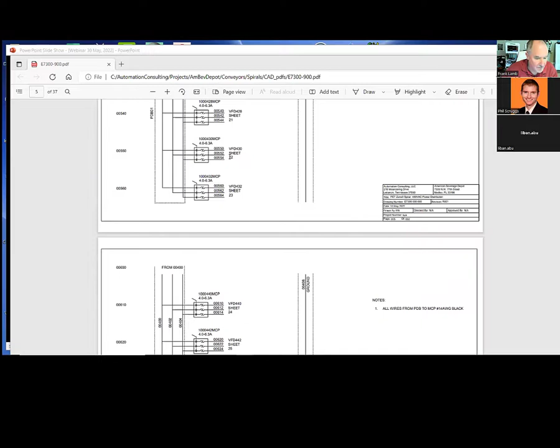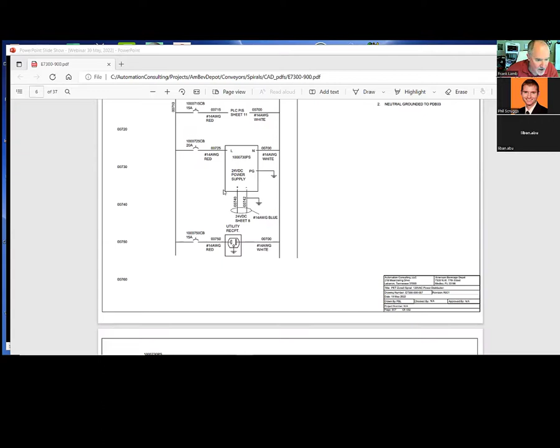And then here you can see power going out to the 120 volt transformer. And then you get into the 120 drawings. And I always refer back, comes from sheet 6. And there's our big power supply. It's 20 amp, it's not huge. He actually had a 40 amp on site, but I didn't want to overload the transformer. But if they want to change that on the fly, they easily can, but they would have to increase, right, this circuit breaker. They would have to increase the size of the wiring, right, for all this. So if they make that change, then I'll go modify the drawings at that point.